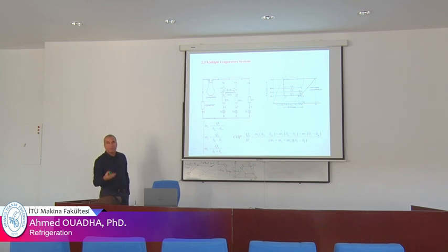So it will produce a refrigeration effect at different temperatures: this temperature, and this temperature. Then the vapor leaving evaporator three, for example, will undergo an expansion in the back pressure valve to return to the aspiration of the compressor. The same thing for the second evaporator. And here, the compressor will aspire all the vapor coming from the three evaporators.